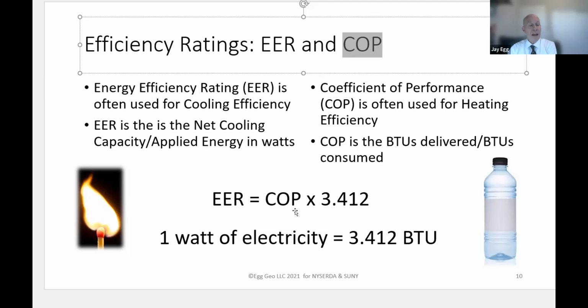The BTU rating, for those that haven't studied thermodynamics, is very simple. One wooden matchstick burned from the top to the bottom is 1 BTU of energy, or 1 British thermal unit. 1 British thermal unit is the same amount of energy it takes to raise 16 ounces of water 1 degree Fahrenheit. So to correlate that to something we use more commonly in the world, a watt of electricity is equal to 3.412 BTUs. So a watt of energy is equal to about 3.5 matches burned. So if you put 1 watt of energy into a 16-ounce bottle of water, it will raise that bottle of water 3.4 degrees Fahrenheit, which you can easily correlate to Celsius.